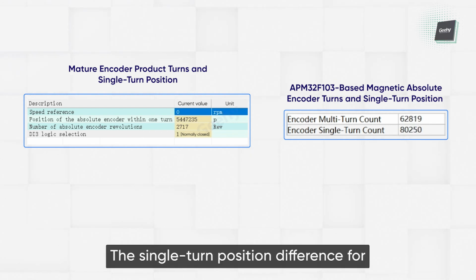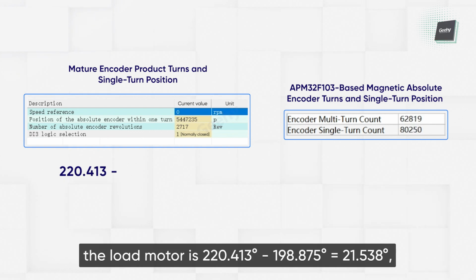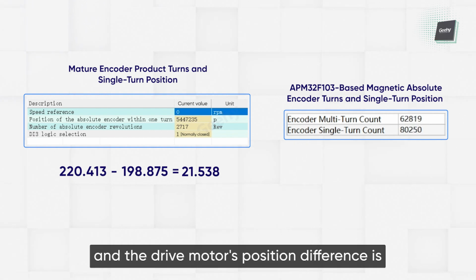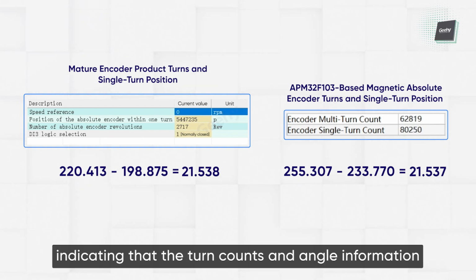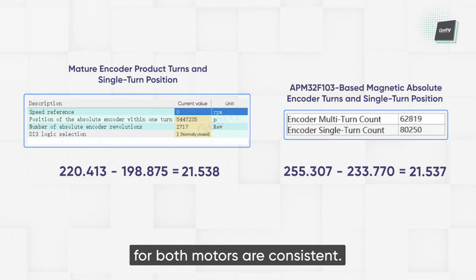The single turn position difference for the load motor is 220.413 degrees. Subtract 198.875 degrees equals 21.538 degrees. And the drive motor's position difference is 255.307 degrees. Subtract 233.77 degrees equals 21.537 degrees, indicating that the turn counts and angle information for both motors are consistent.